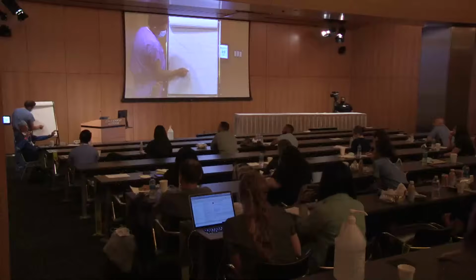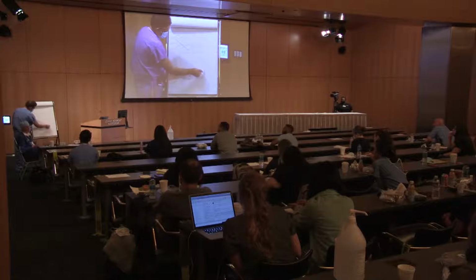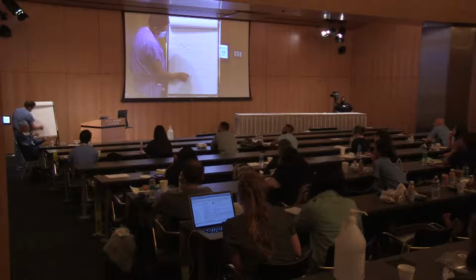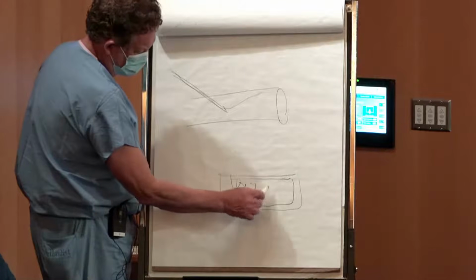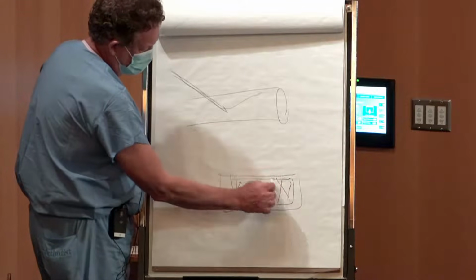But it's not the best option. Generally speaking, if you're pulling a wire and you get resistance, don't keep pulling. Same thing can happen with glide wires, with the hydrophilic coating. You really never want to put a hydrophilic wire through a metal needle, they're meant to go through plastic stuff. You pull a glide wire out of a steel needle and you can shear and peel all of that hydrophilic coating off and leave it stuck inside somebody. So pulling out things where you can peel off the sheath is a bad idea. Definitely don't do it with the micro wire.